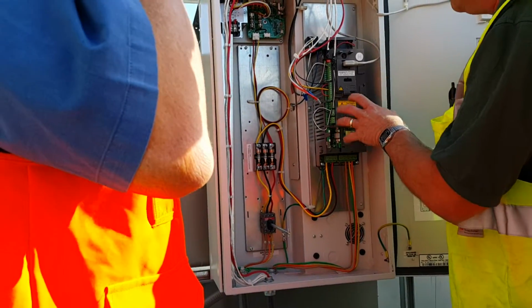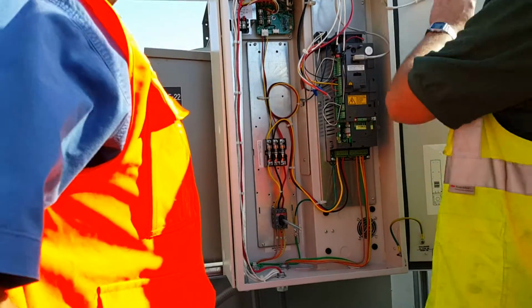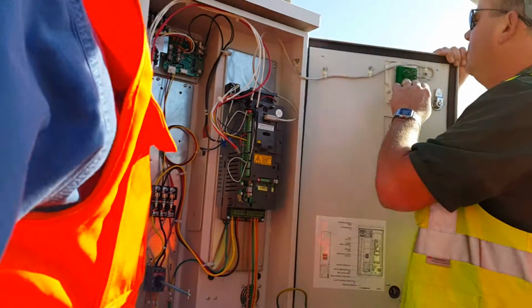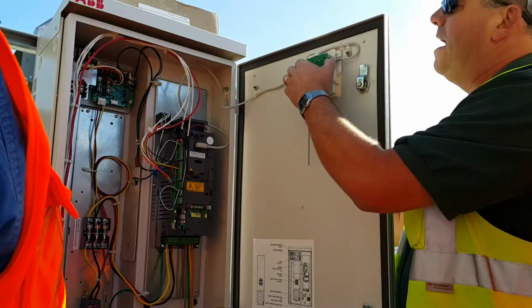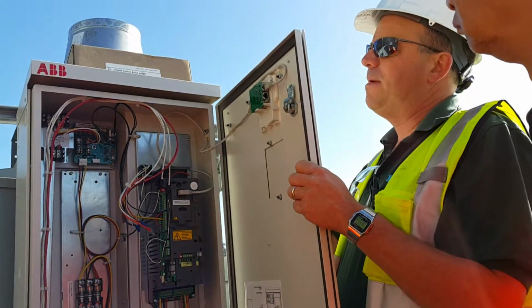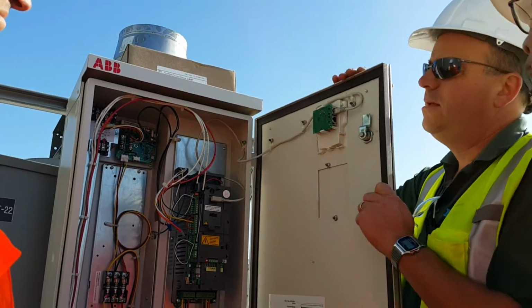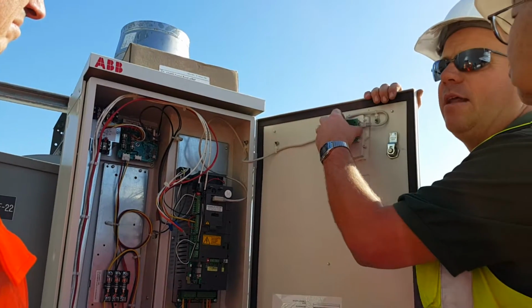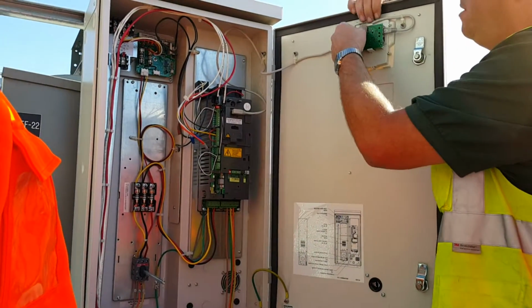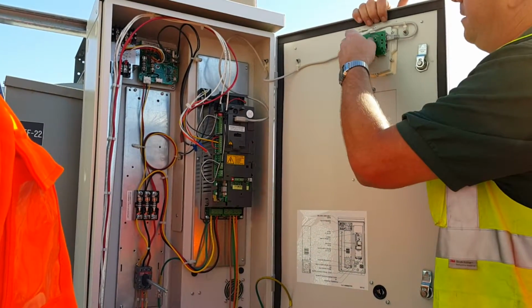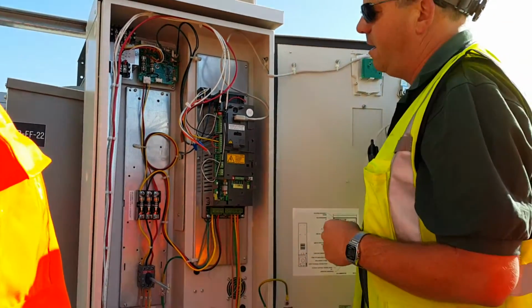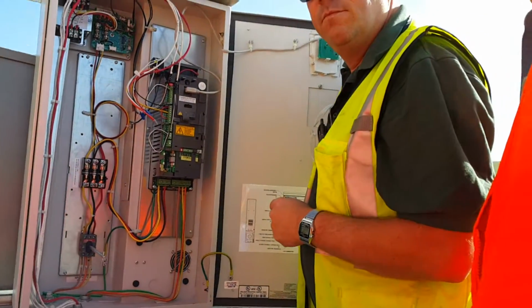Then we have the drive itself. This is the connection between here and the keypad. Once in a while, like I said, sometimes this board pops back. So if you take the keypad out and you put it back in and it doesn't come up, take a look to see if this board didn't snap out. That'll happen sometimes on this particular type. And we just gotta make sure these are actually snapped in there. Not a big deal. What's the purpose of that panel coming off?